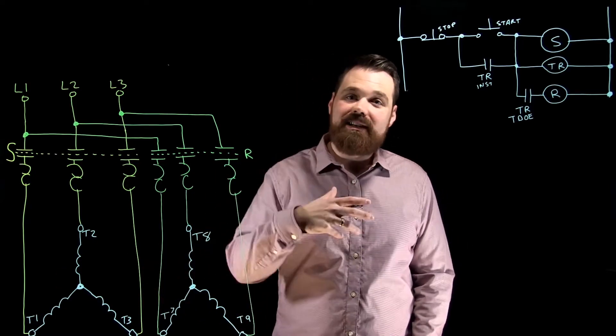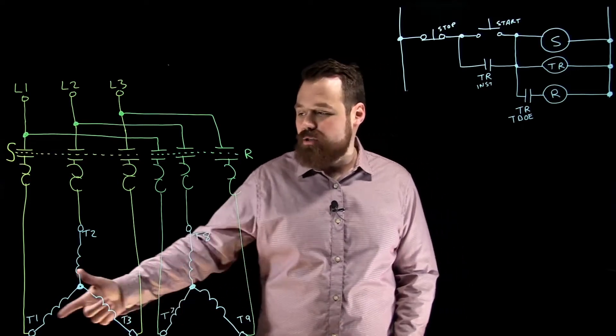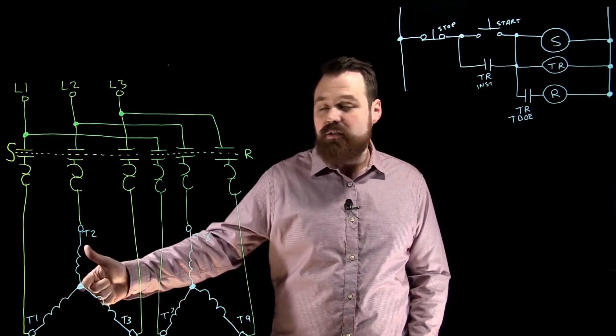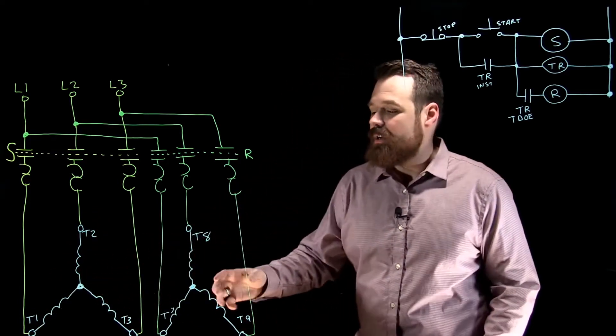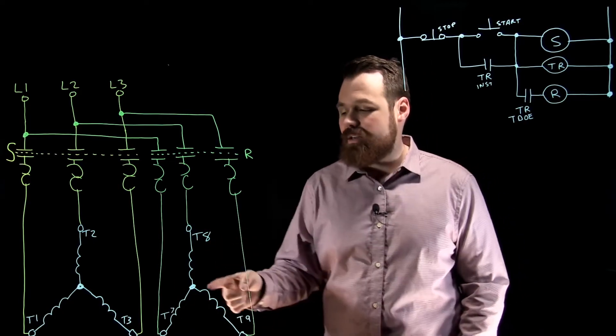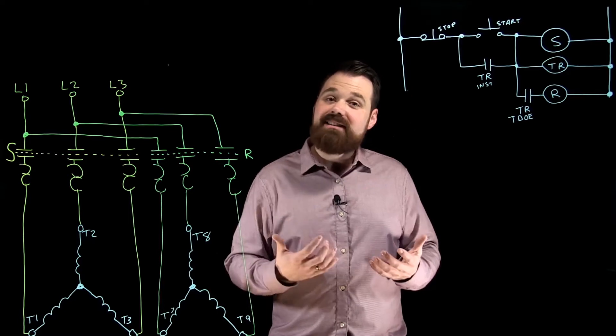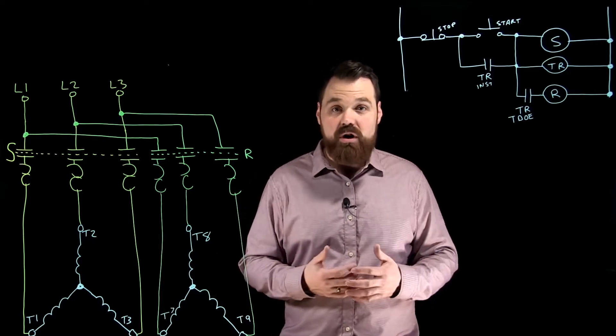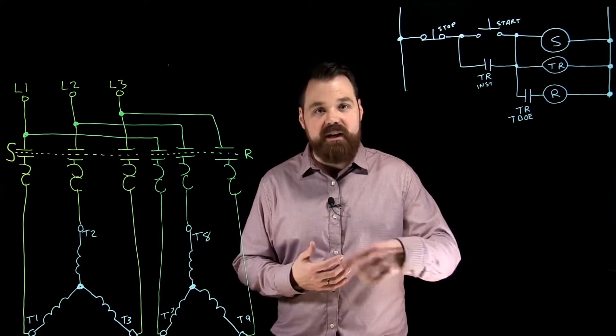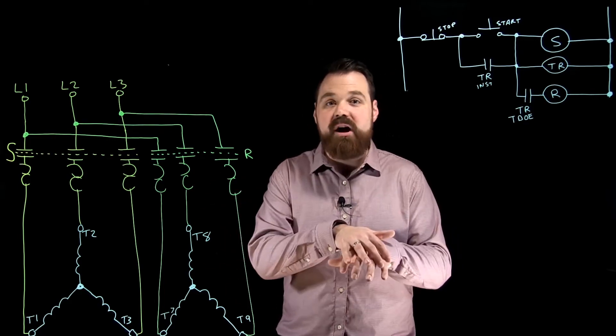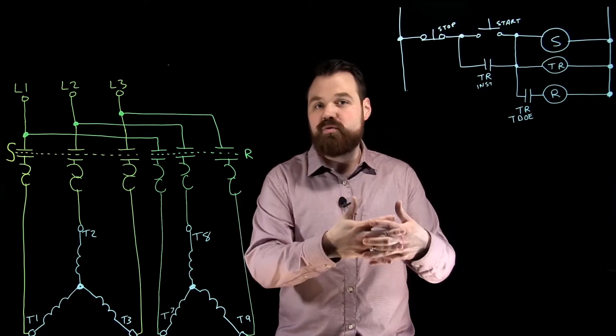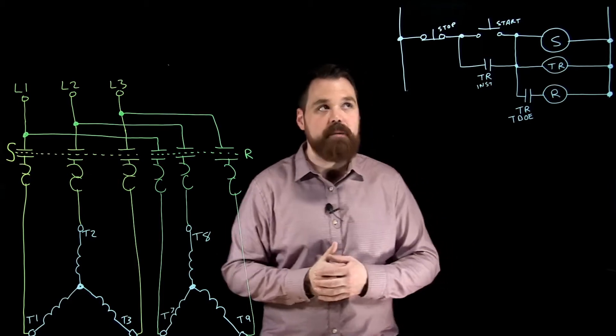So the motor leads that we'll see brought out to that junction box are T1, T2, T3, there's the internal Y connection, and then T7, T8, and T9, again with their internal Y connection. Now the idea here is we're going to basically start half of the motor to get it up to spinning, and then we're going to bring the other half online for our full voltage run or our full speed, full load run.